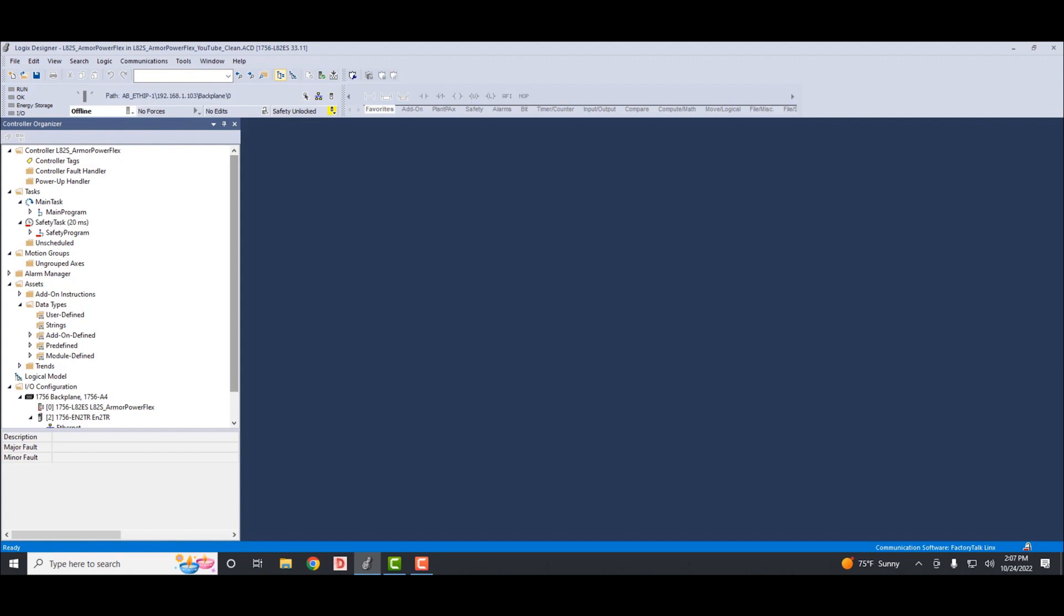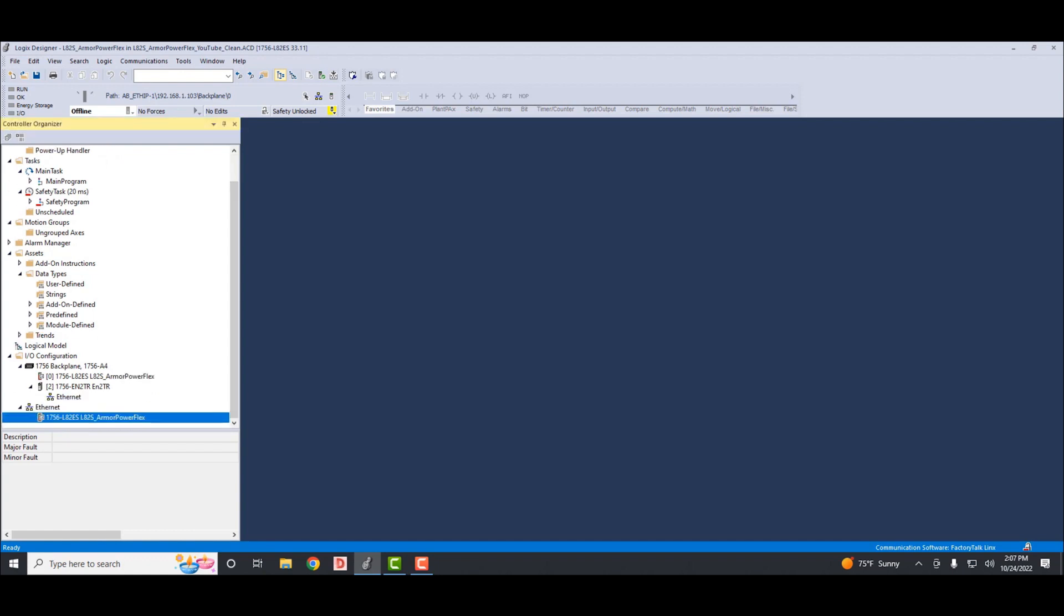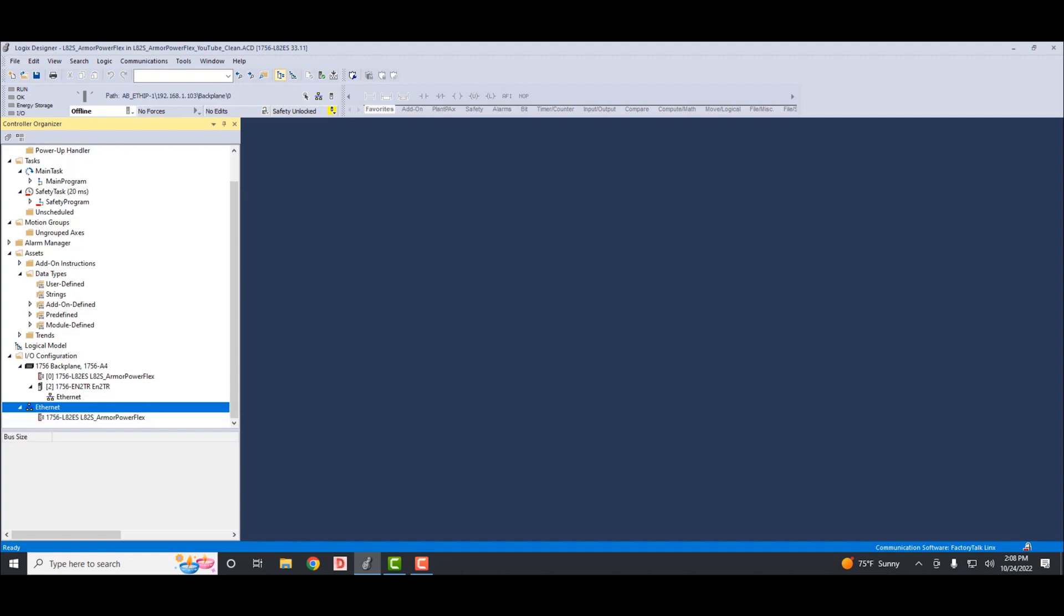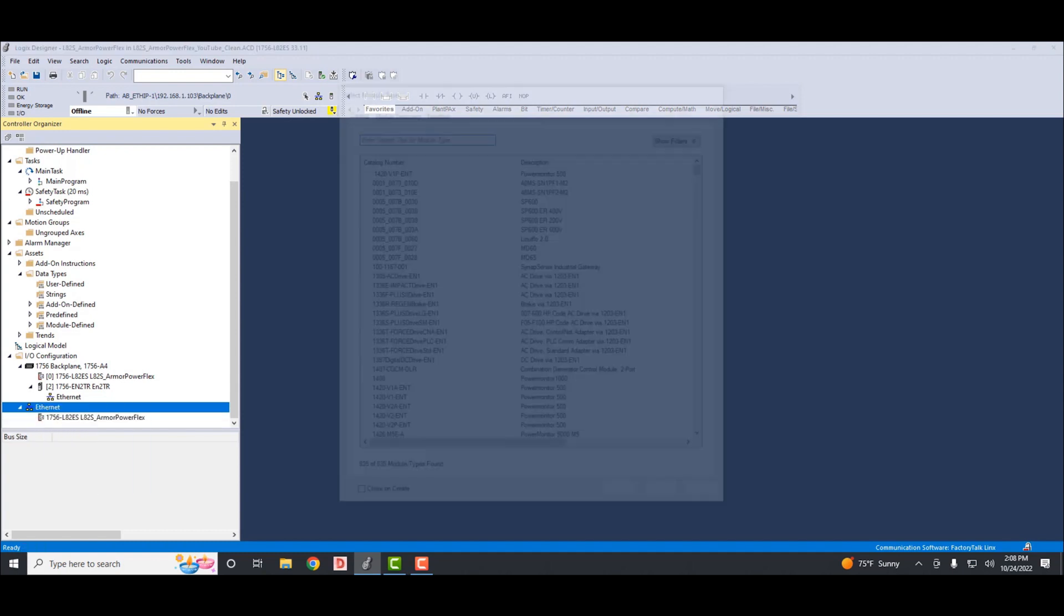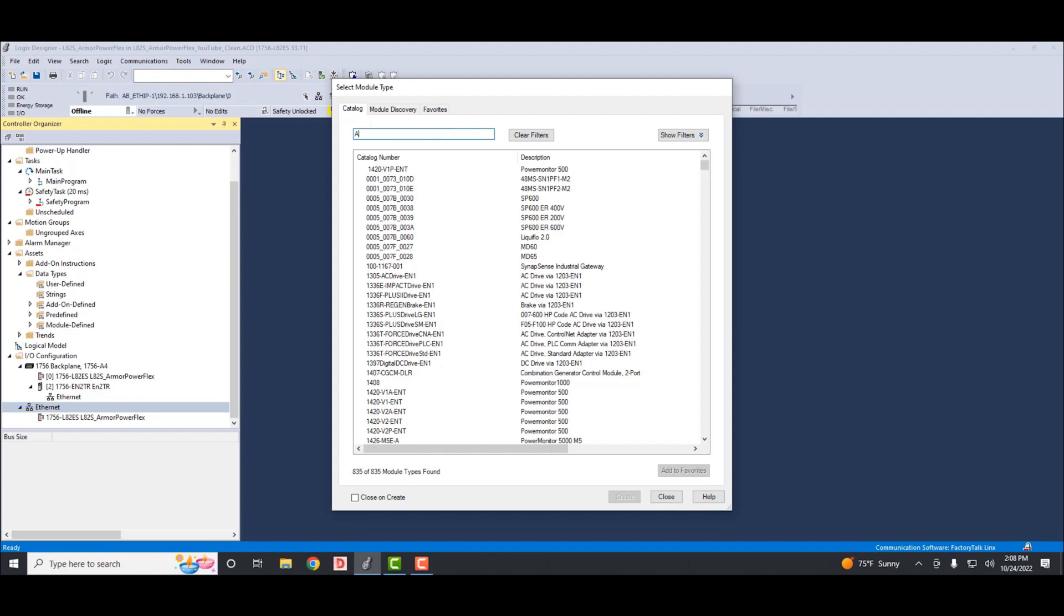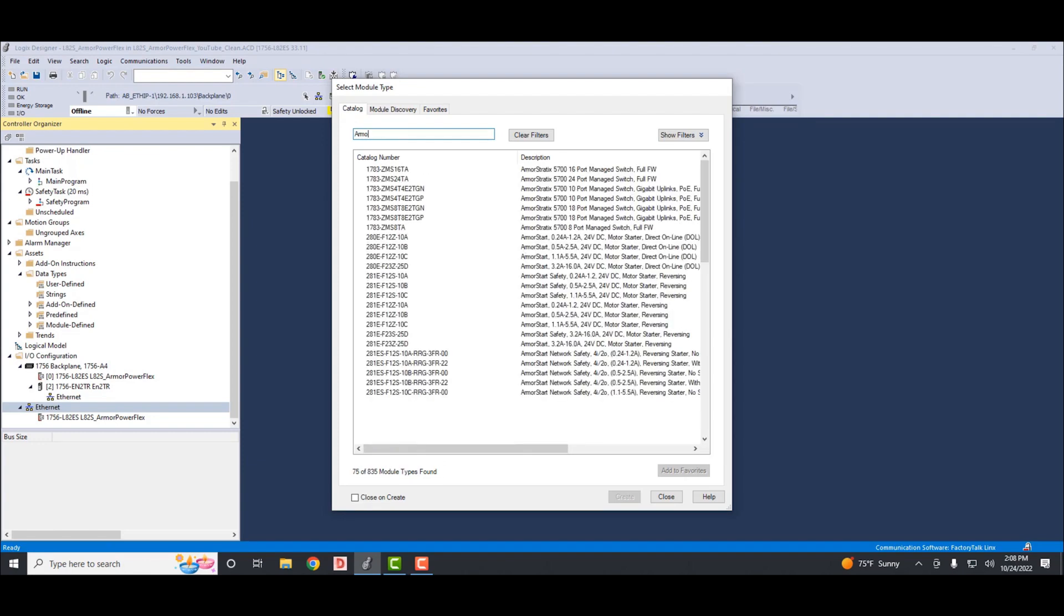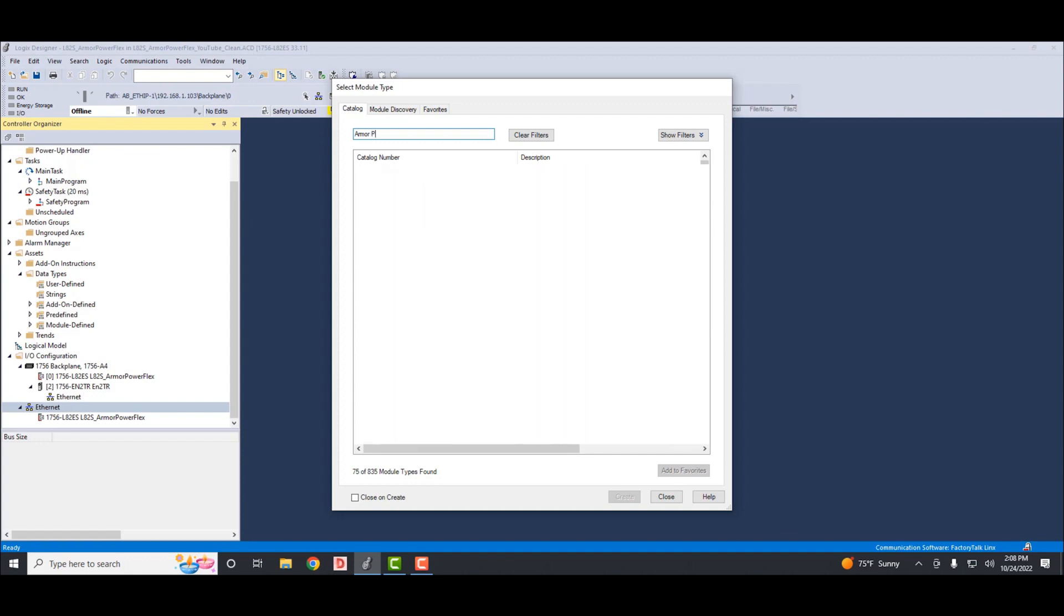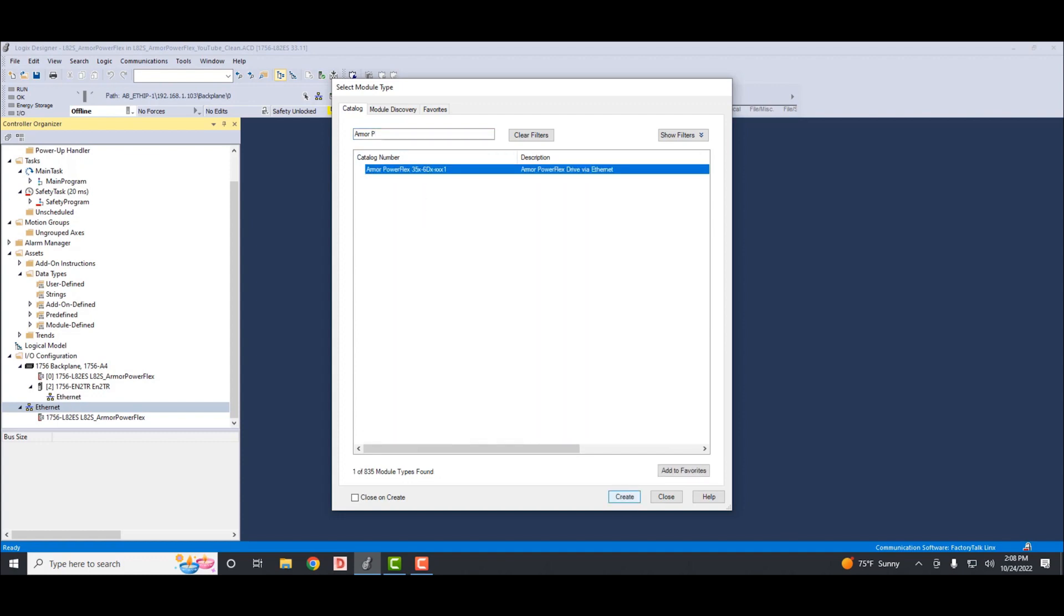Here I have created a project using an L82ES processor and an EN2TR module in the rack. The L82ES has a gigabit Ethernet port built into it which the Armor PowerFlex is plugged into. My laptop is plugged into the EN2TR module in the rack. The Armor PowerFlex IP address is already set up, so we don't need to go through that. To add any module, we'll right-click on the Ethernet, select new module. Up top, we'll use the filter and we'll type in Armor P. That'll filter out all but the Armor PowerFlex.